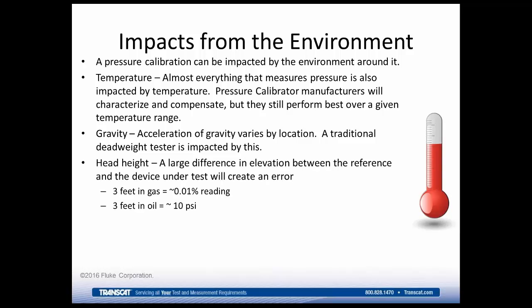Another thing to consider is what we call head height. That is the difference in vertical elevation between the reference and the device under test. And what it will do is create an error. Basically, the weight of the fluid will generate its own pressure. And you can think about that as if you're in a swimming pool, the pressure at the top of the pool is much less than the pressure at the bottom of the pool. Same thing applies here, and the phenomenon occurs whether it's gas or oil. Even a column of gas can create a pressure. Even though we don't think of it as weighing anything, it really does.